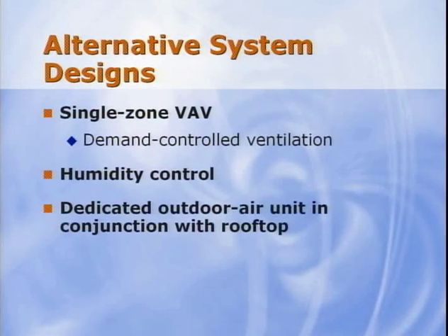So from a system design standpoint, single zone VAV is often used in systems today and provides energy reductions, especially when used in conjunction with demand-controlled ventilation. And there are more energy-efficient humidity control alternatives available today also. You know, when we speak of system design alternatives, some of them sure feel a lot like control options. That line between system design and system operation is becoming fuzzier all the time. The bottom line is that the sensors and controls need to be installed for the system to operate efficiently. Okay, speaking of controls, let's ask the team to cover some optimized system controls.